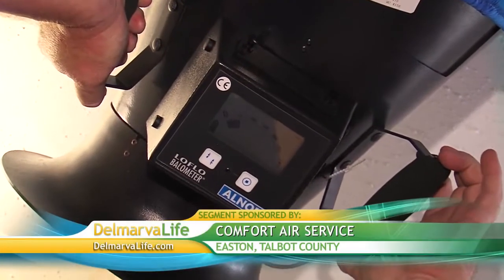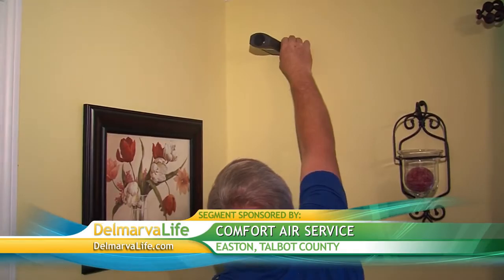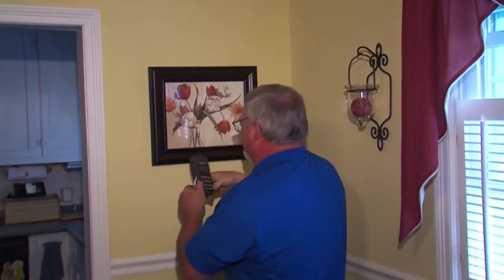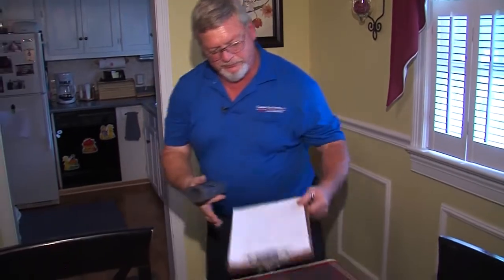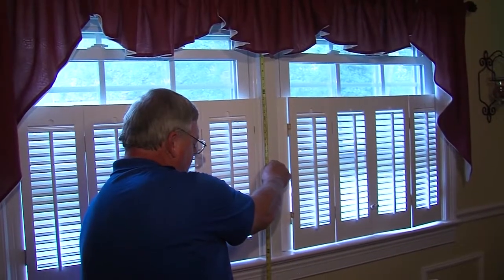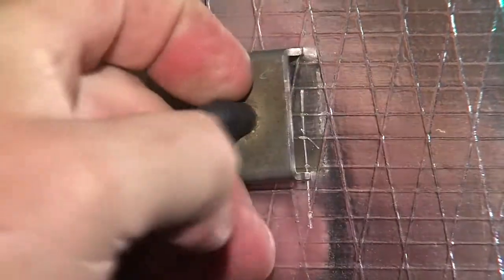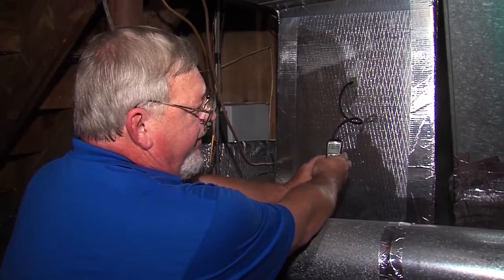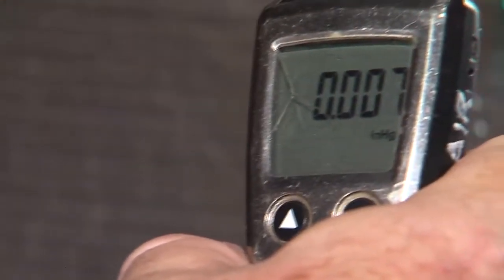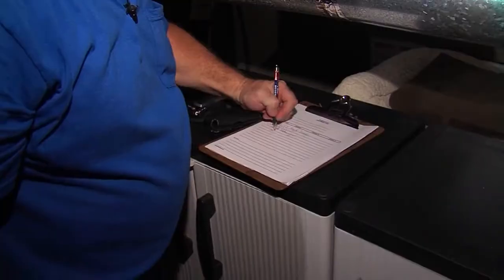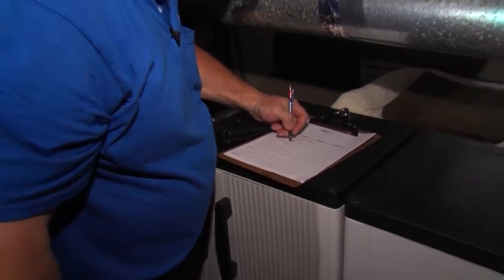In addition to testing the airflow, Comfort advisors also do what's called a Manual J load calculation. We measure up the whole house, so we know exactly the size of all the rooms, how high the ceilings are, what levels of insulation there are in the walls, the ceiling and the crawl space. All those things impact the heating and cooling load of the house. Windows, what kind, single pane, double pane, triple pane. The static pressure in the ductwork is also determined. And the higher the pressure, the harder the machine has to work to get the same job done.